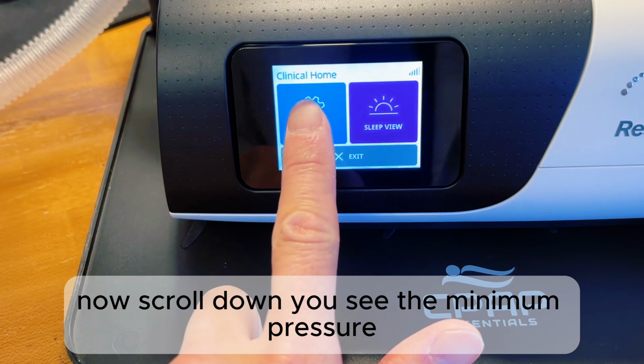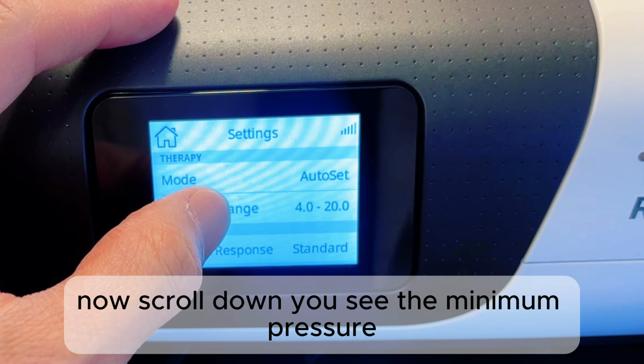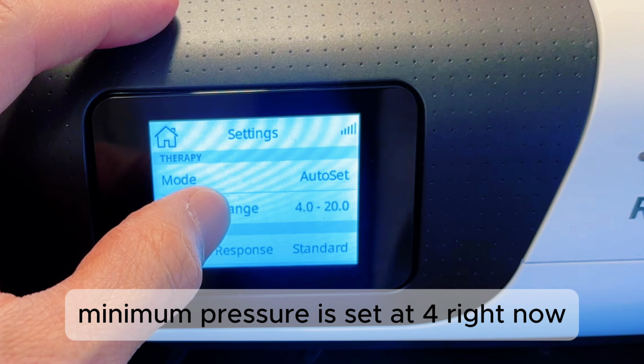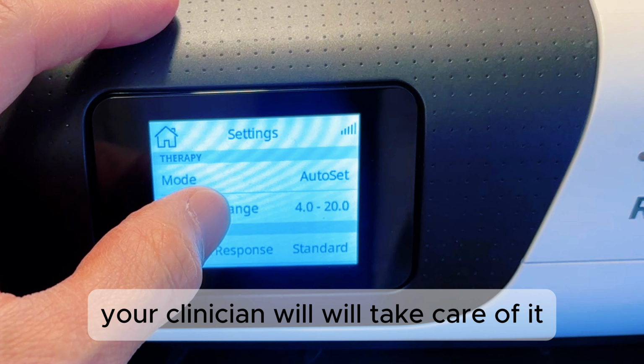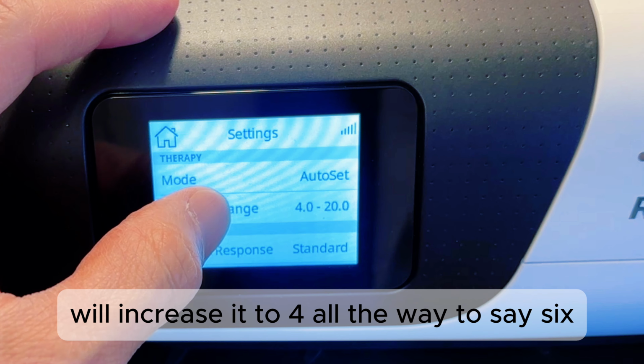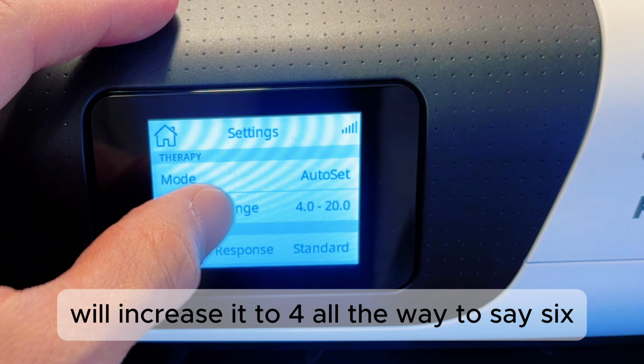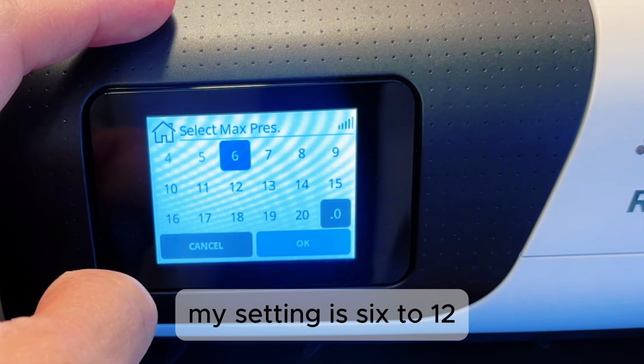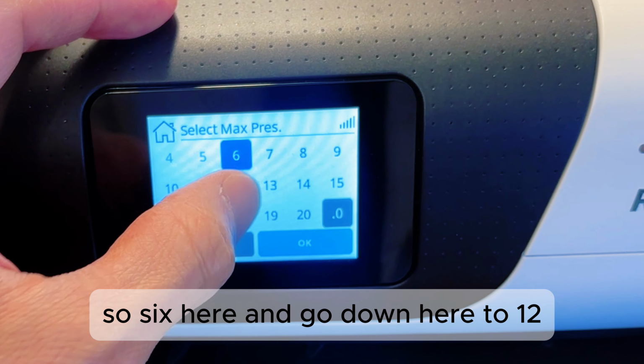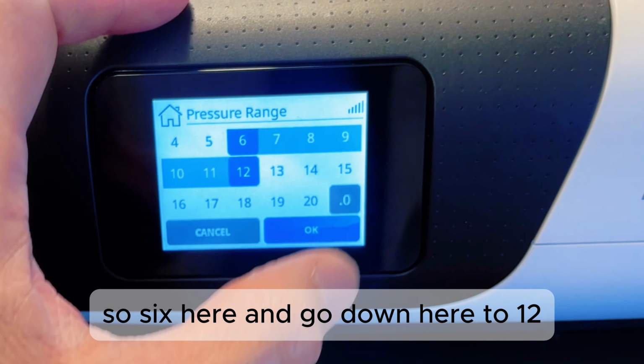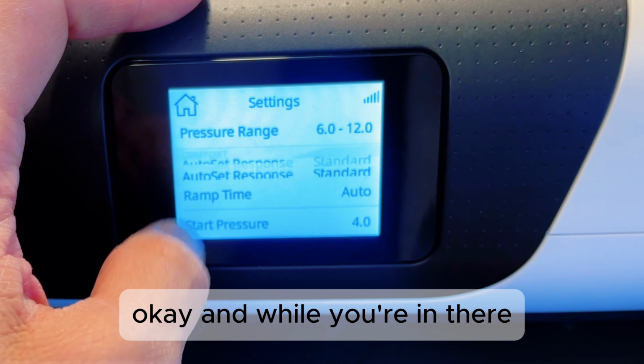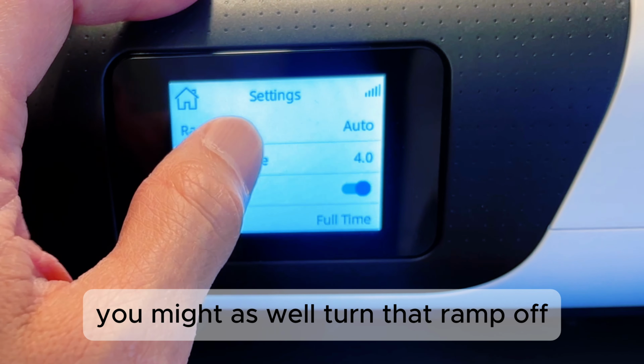Now, scroll down, you see the minimum pressure. Minimum pressure is set at 4 right now. Your clinician will take care of it. We'll increase it from 4 all the way to say 6. My setting is 6 to 12. So 6 here and go down here to 12. Okay. And while you're in there, you might as well turn that ramp off.